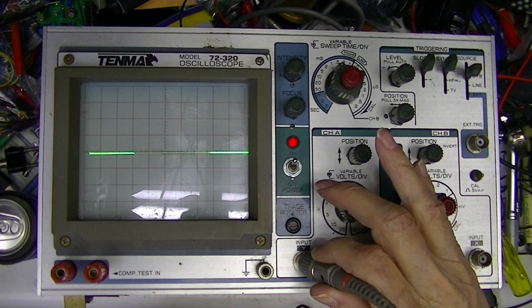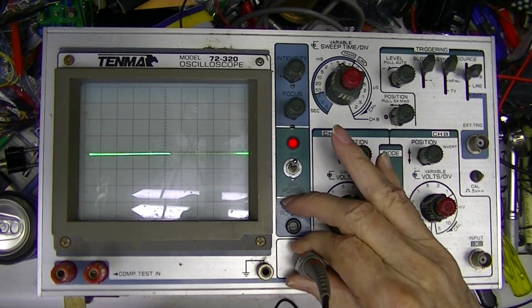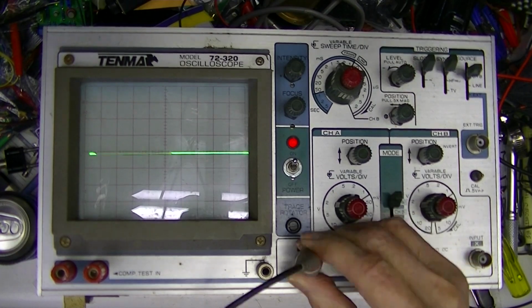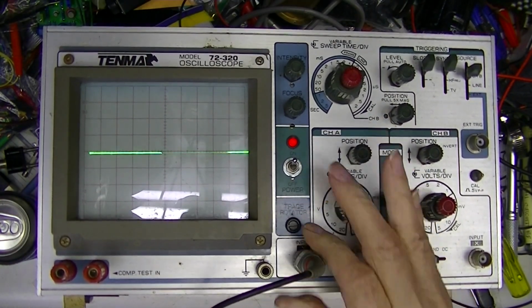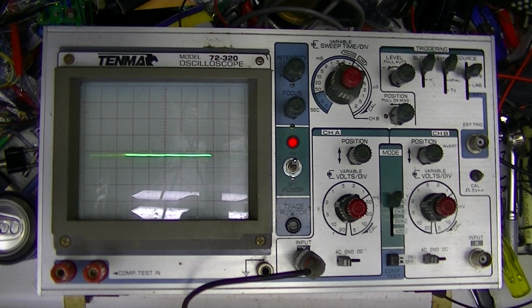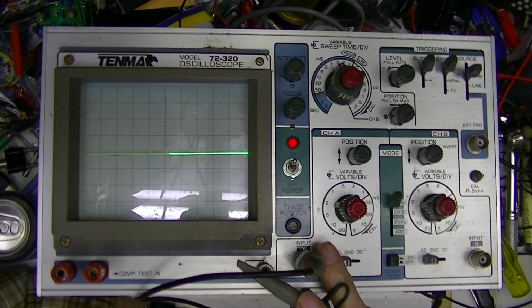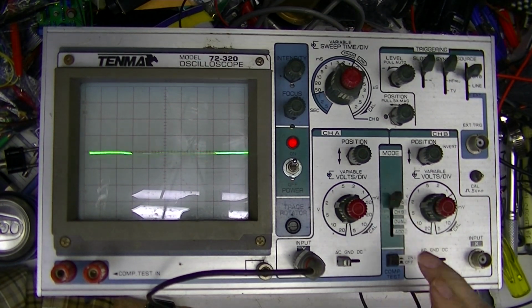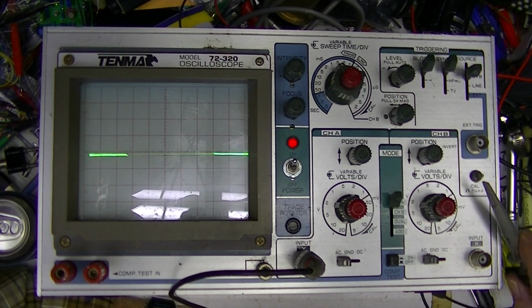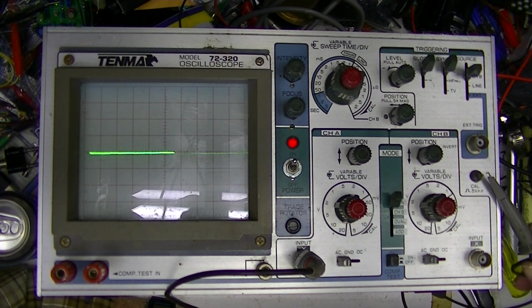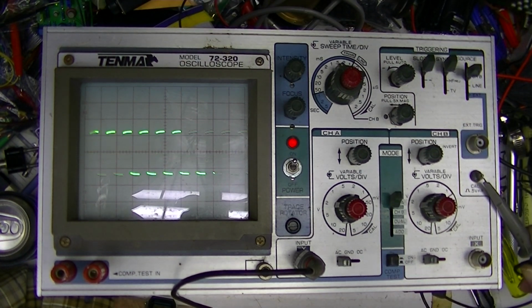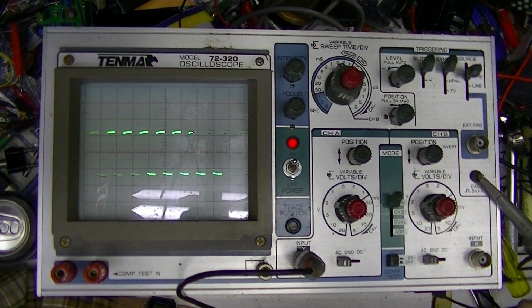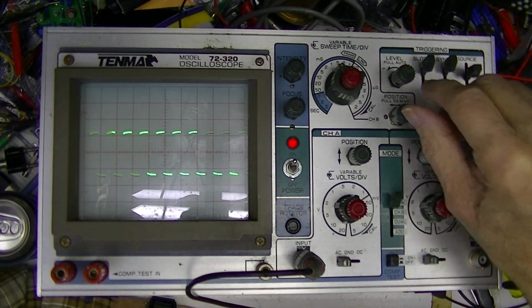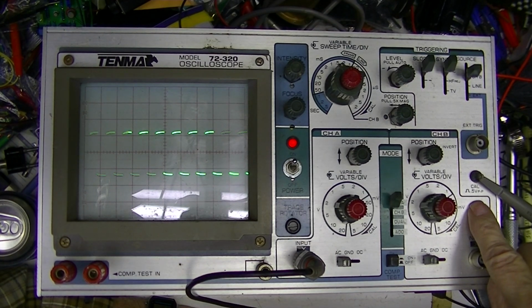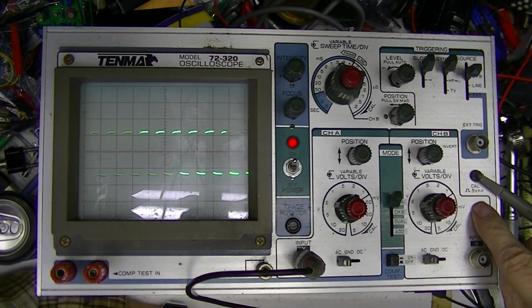So I'm going to put the probe in channel A, lock it, with the probe hooked to channel A, the switch in channel A position. I'll put the hook on this calibration signal. Now, according to this calibration signal, it says it's a half a volt peak to peak. Well, that's peak to peak.